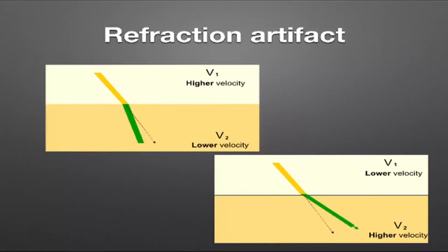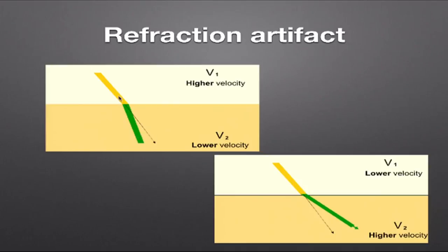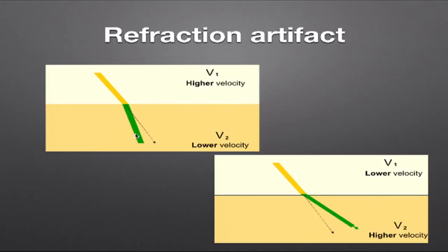Refraction artefacts can create range ambiguity. Because the ultrasound machine assumes waves travel in a straight line, a refracted wave may display a structure in the wrong position — where the machine thinks the structure is located is actually different from where it truly sits, leading to structures being displayed in slightly the wrong location.